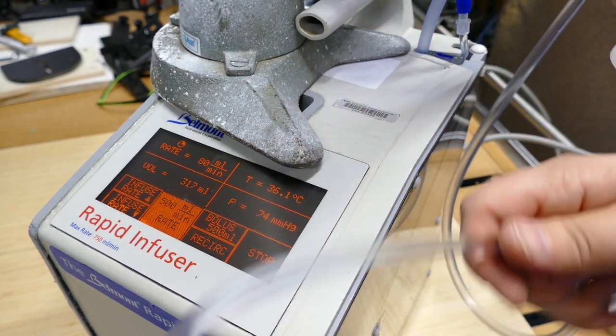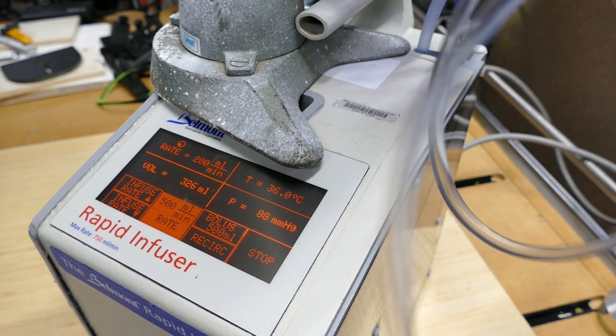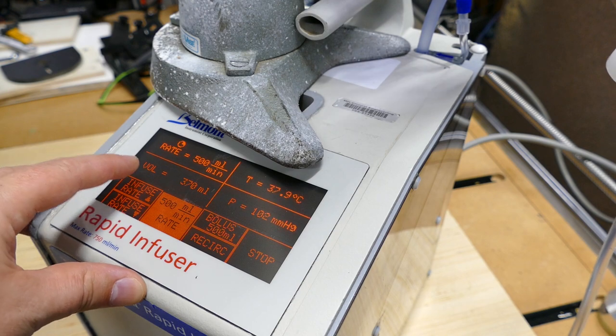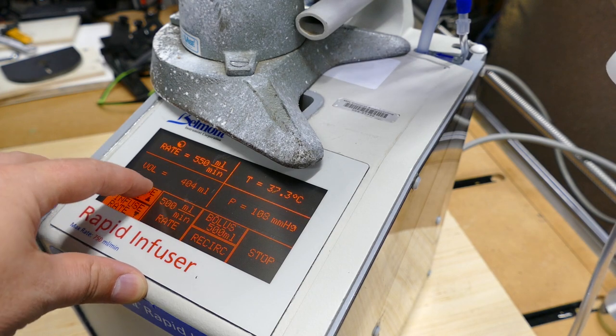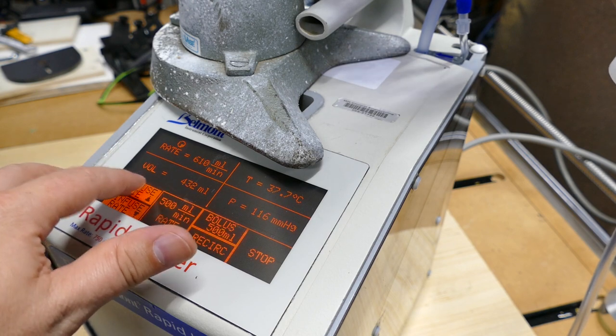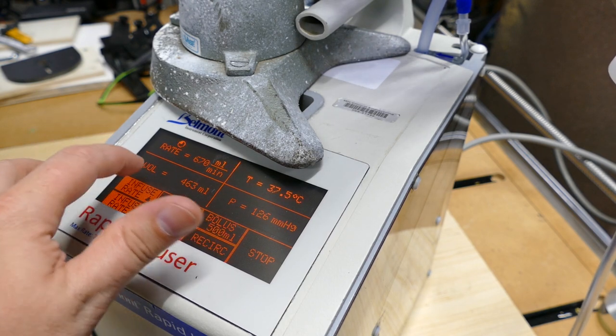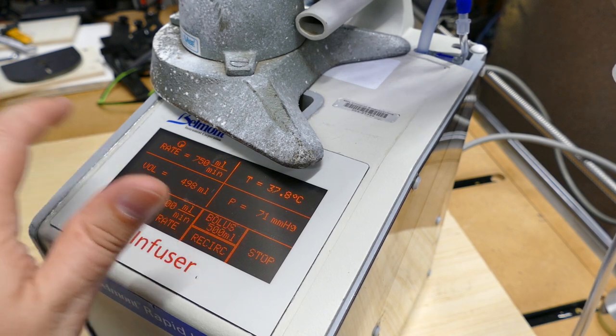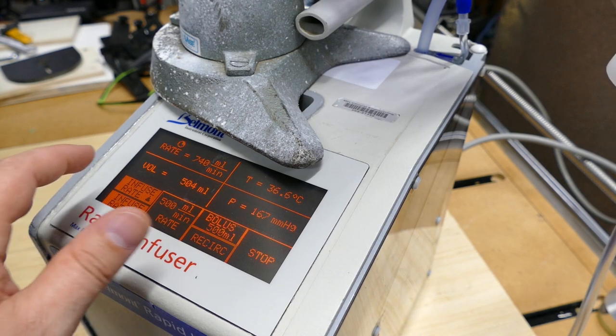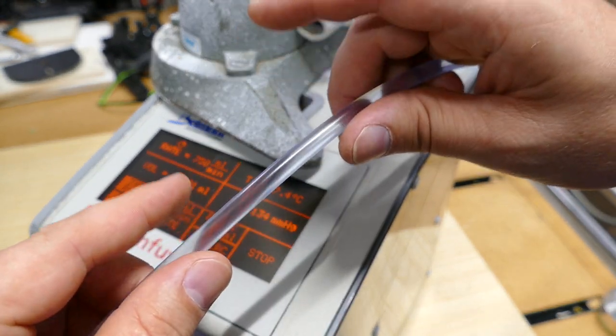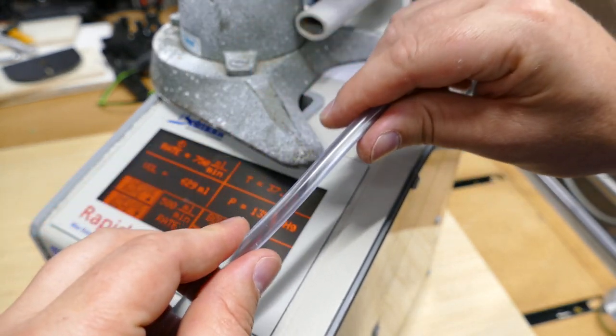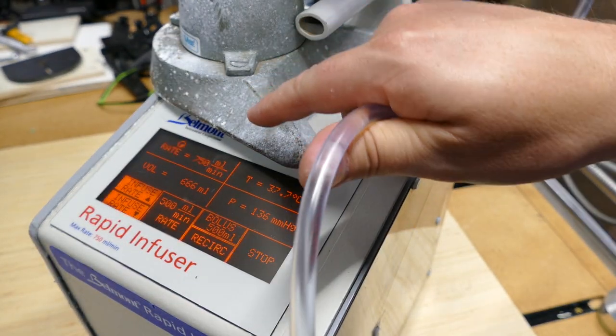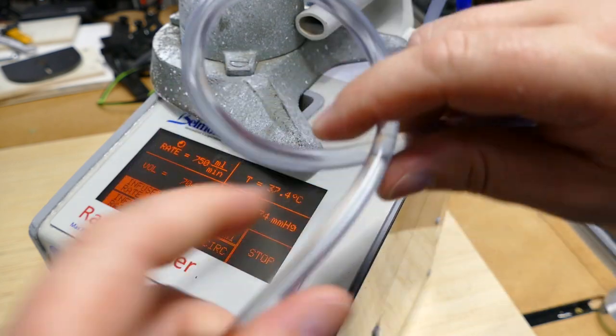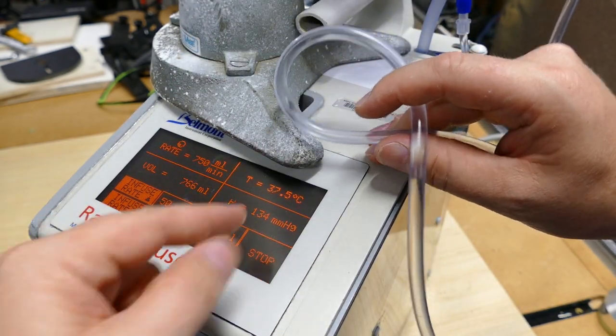I can feel the line getting very warm. It's going to get body temperature, 37 degrees. I'm going to go ahead and turn up the infusion rate. We're going to test it at its maximum infusion rate and its minimal infusion rate. The maximum rate is going to check all the sensors and the pump to make sure that they can compensate and keep up. The minimum rate is actually going to test more so the pump and make sure that the pump can handle pushing and squeezing against this tubing at a low rate. You're going to get errors at your high flow rates, usually for sensors when they're starting to throw errors. And you're going to have errors at a low flow rate, mainly for the pump motor, because it's going to stall out.